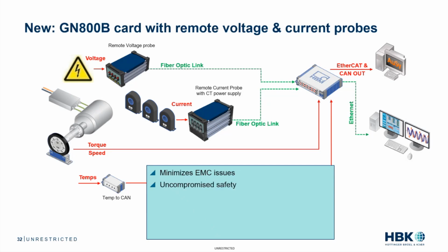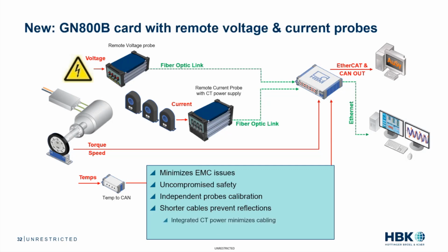You've got uncompromised safety. You also have independent probe calibration, so you don't need to send your mainframe back for calibration. You just send that remote probe, whether it be a voltage or current probe, and you can maybe have a spare one handy to continue to make measurements, and that makes it a lot easier for calibration. Shorter cables are going to prevent reflections, so you just have a nice short cable that goes from the measurement point to the probe. You don't have to run a wire or cable all the way back to the data acquisition system because you've got that fiber optic link.